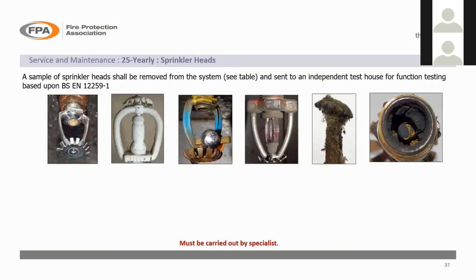There's a sample here. You can see various sprinkler heads where they've been overpainted and things like that. These are some of the heads that have been sent into the FPA. Some barely recognisable as a sprinkler head at all, to be honest. And these are the worst case. I mean, most of the sprinkler heads that get sent in, sometimes even the very, very old ones, they pass the test, so that's the good news.